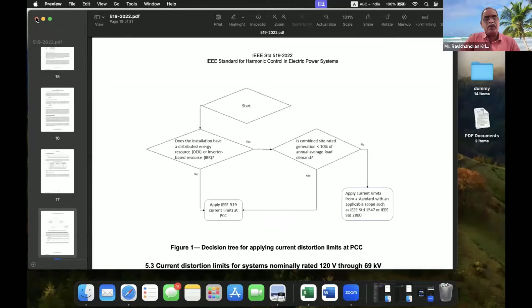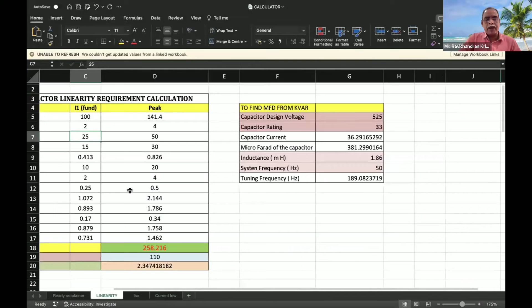And secondly, the detuned reactor has to be designed properly. I am showing one of the screens here. This is the important factor we have to find: linearity. See, for a detuned filter, for example, when designing with a 525 volt capacitor for the system, and the capacitor rating is 33 kVAR, it will give 25 kVAR delivery, including the 7%. 7% is 189 hertz. I am using the common reactor that is used everywhere, so this is going to give you the 189 hertz frequency. This is a 7% reactor. Only the millihenry of the reactor and this microfarad, these two parameters, are more than enough to decide the 7%.